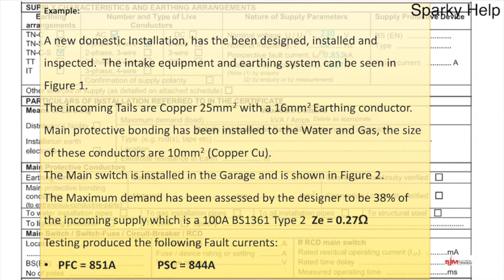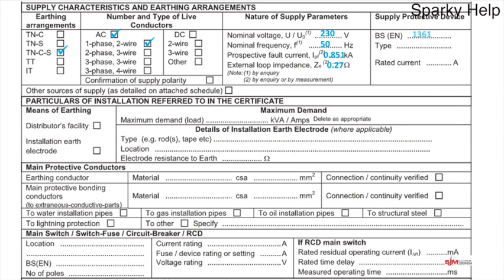I was looking up on these, and the wording they use is that they're for non-skilled people, who should be ordinary people using them. I don't know what ordinary people are doing using them, but that's what they're made for. So BS EN 1361, it could well be different. It could be a BS 88-3. In this case, it says it's a type 2, so type 2 is what we put in, and the rated current of it is 100 amp, which is fairly standard.